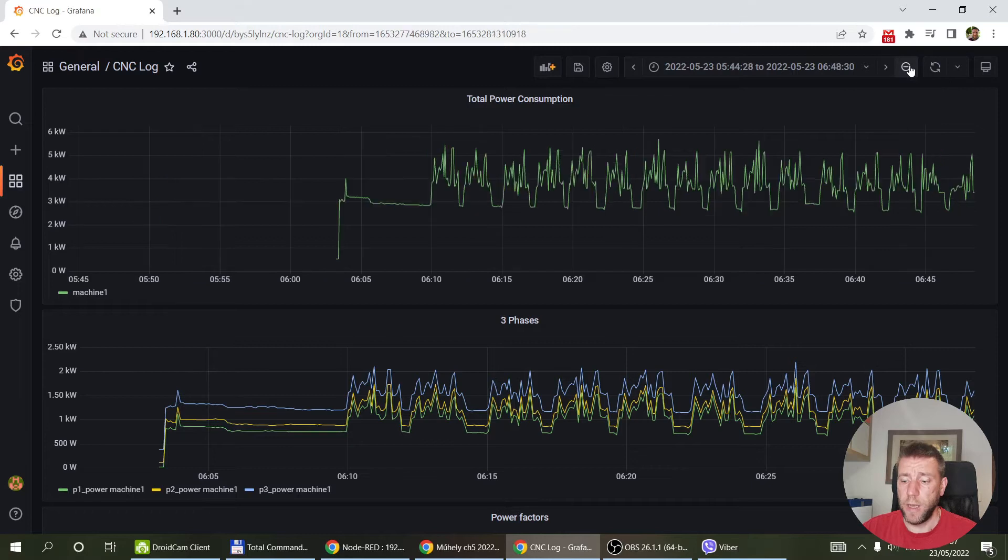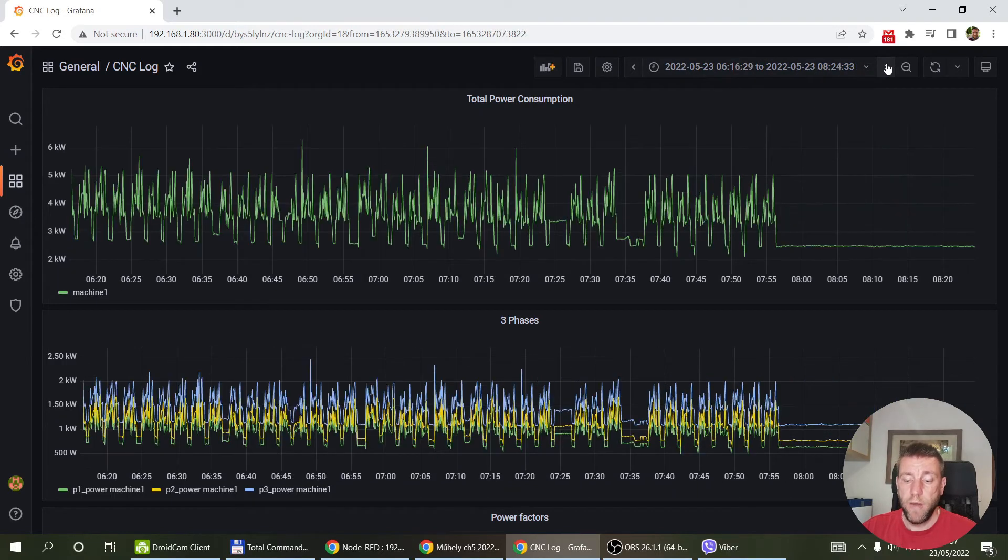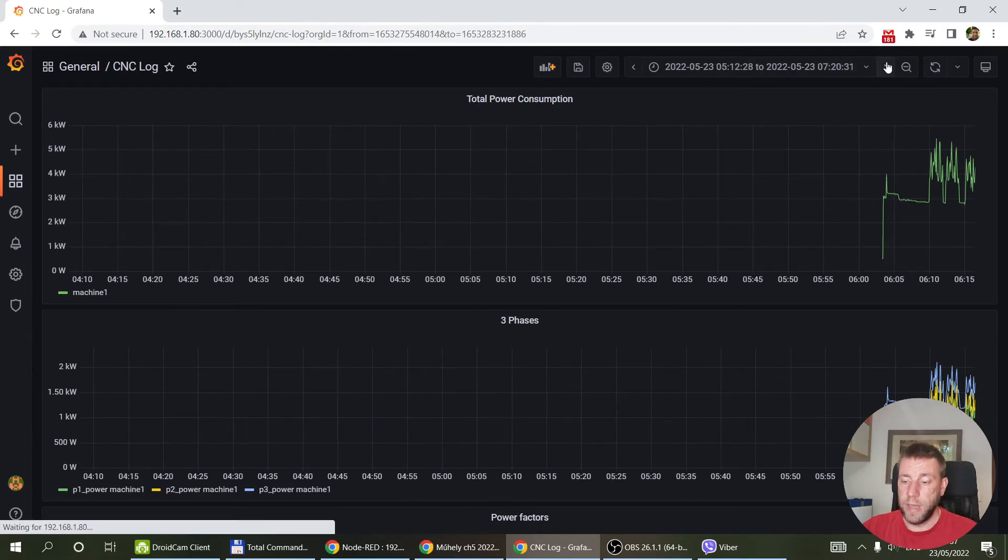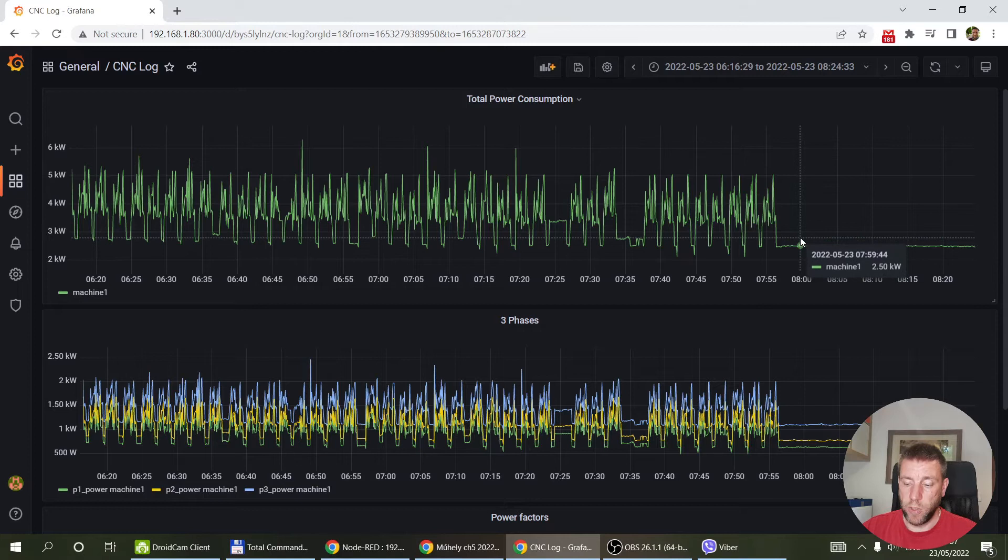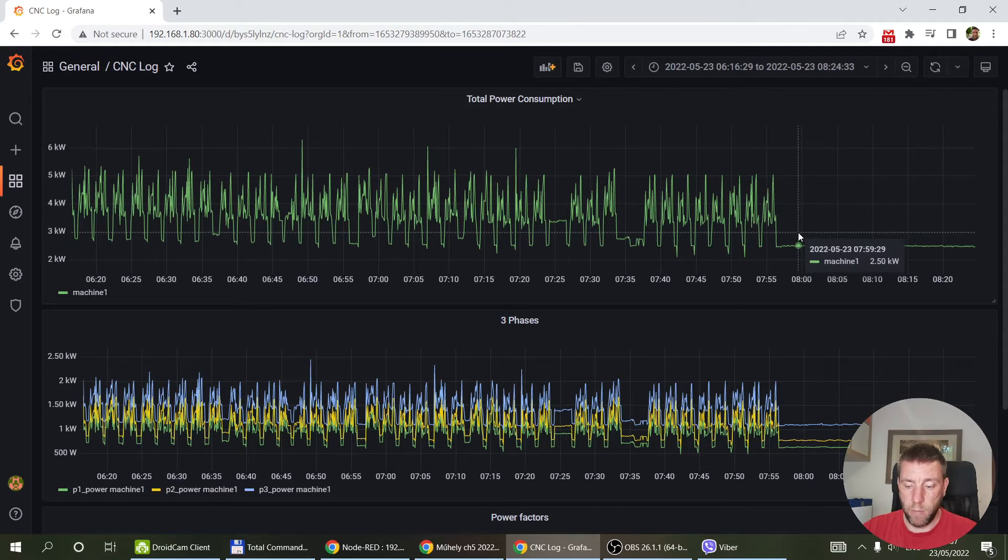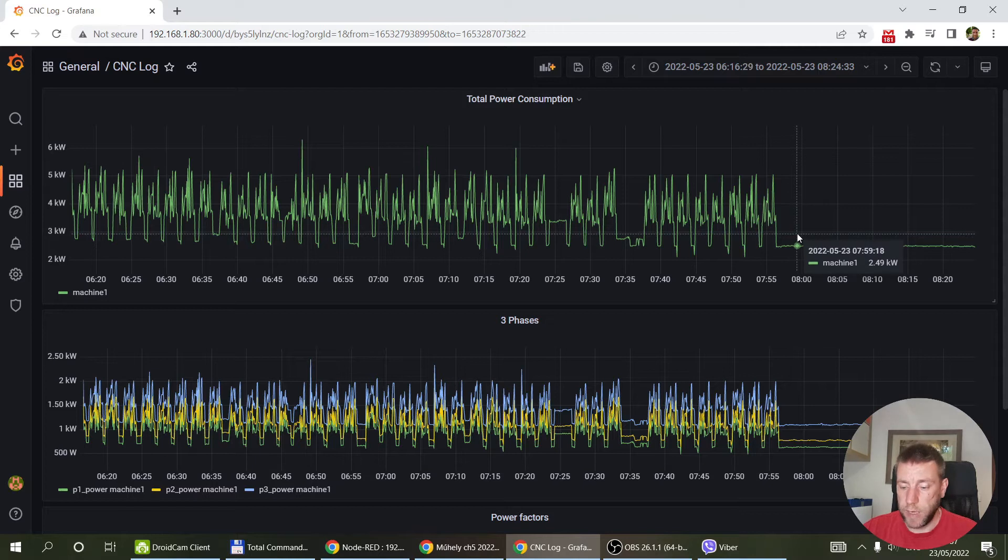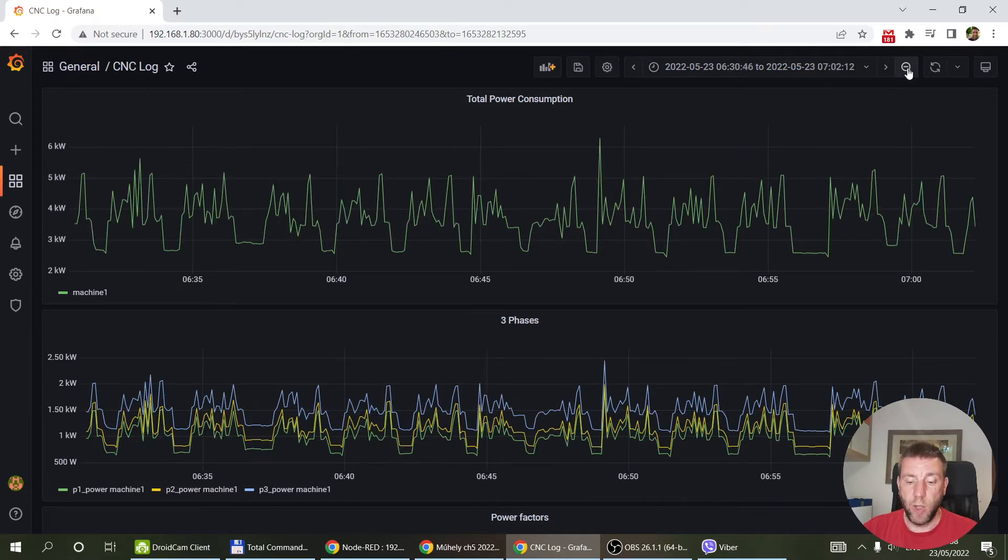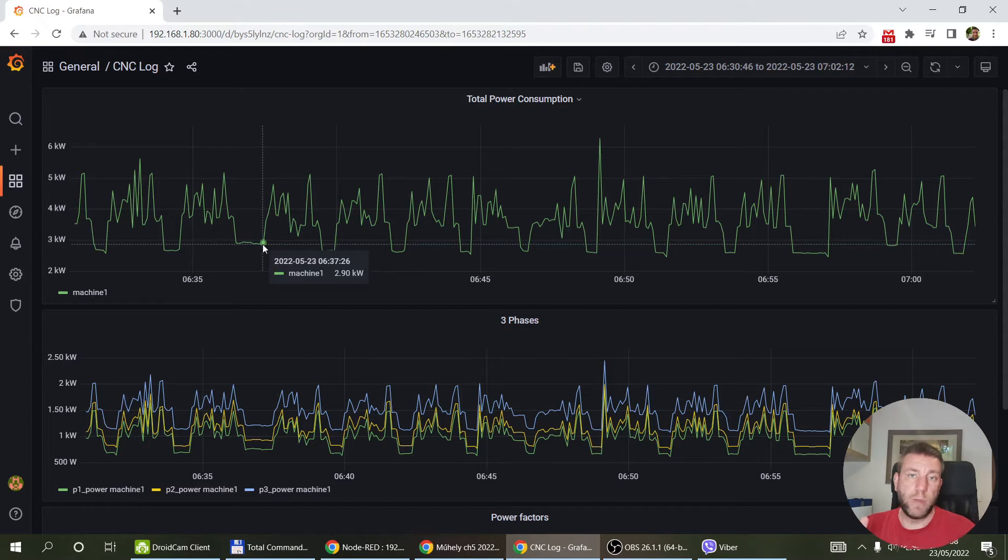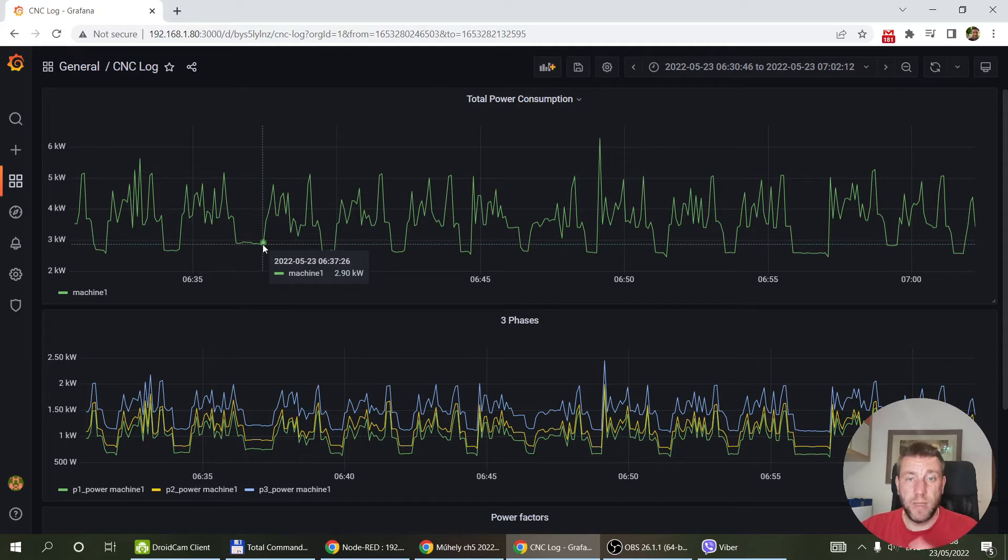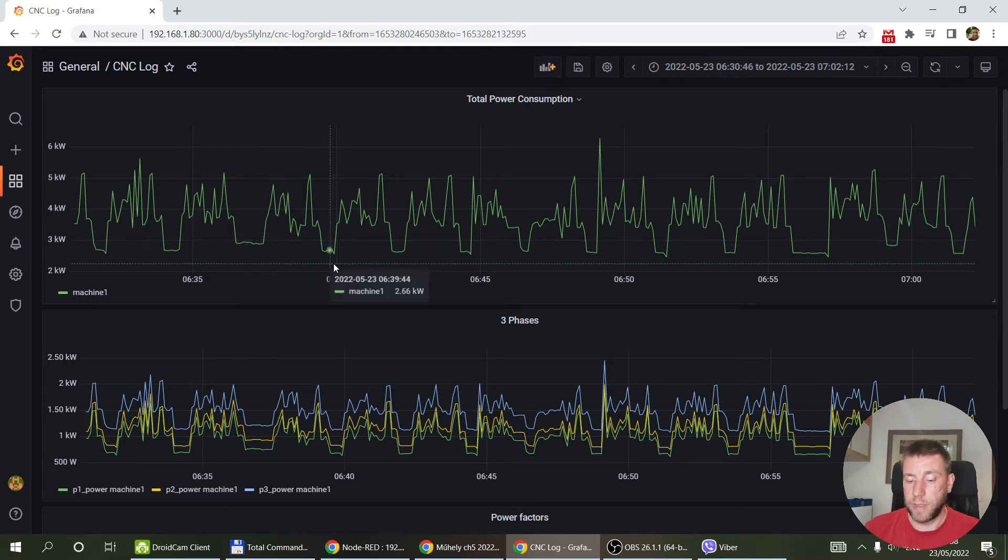Just by looking at this data, my idea was that I'm going to have a flow which is going to detect various phases in the machine. When the machine starts up, it looks at whether the machine idles or not. This is the 2.5 kilowatt benchmark. Then any consumption above that is going to be a cycle running. Between when the cycle starts and stops, it's going to measure the time. There's going to be some threshold. If it's between 110 and 130 seconds, then it's considered to be a valid part. Otherwise it will be a rejected part. Something might have happened, maybe something got jammed and the cycle had to be stopped and restarted. It could still be a valid part, but that's going to be flagged as something else.